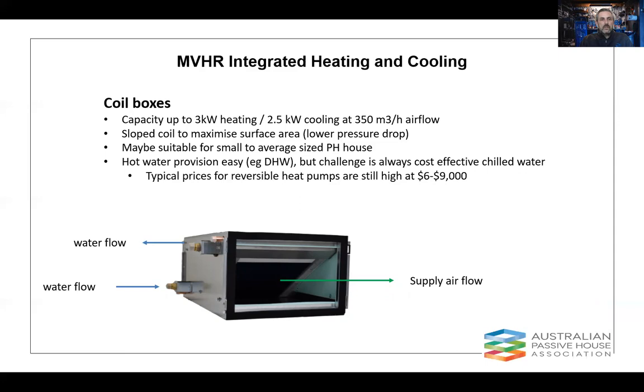So these particular units are designed to integrate fairly seamlessly to the manifolds. So there's no sort of messing around with ductwork. They are chilled water. I've not seen a DX version at this point in time. They are sort of 100% MVHR airflow, so the capacities are limited. We talked about sort of 2 to 3 kilowatt type capacities at that 350 cubic metre per hour flow rate.